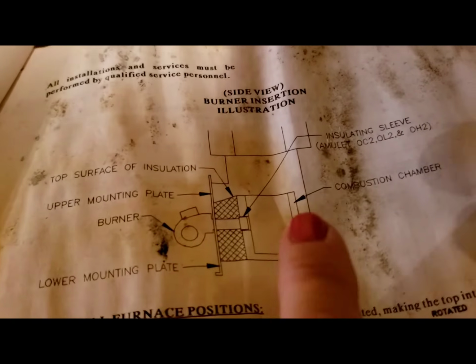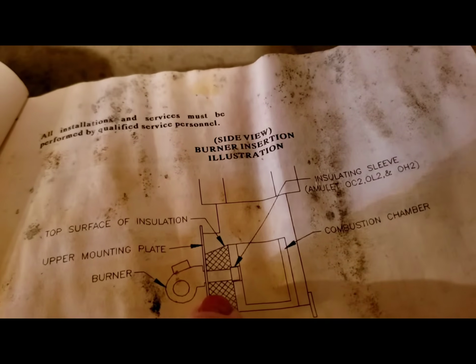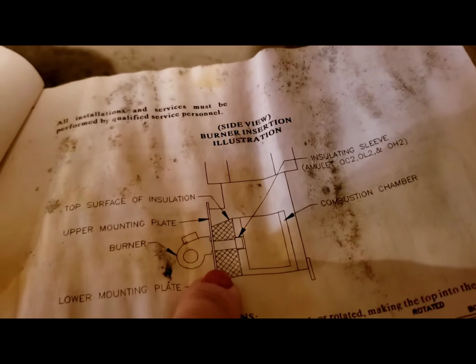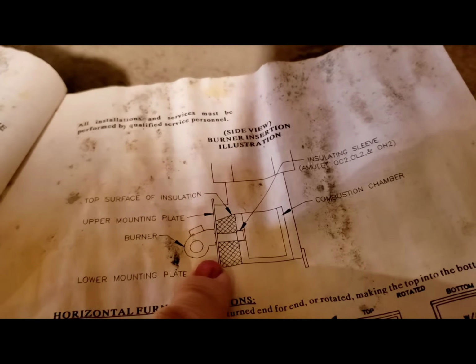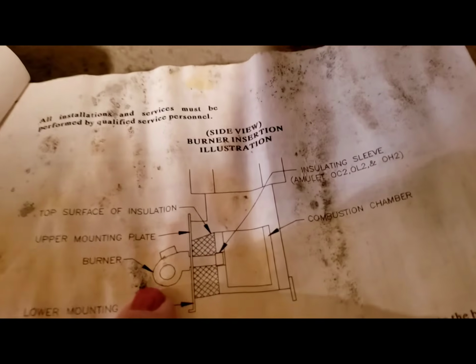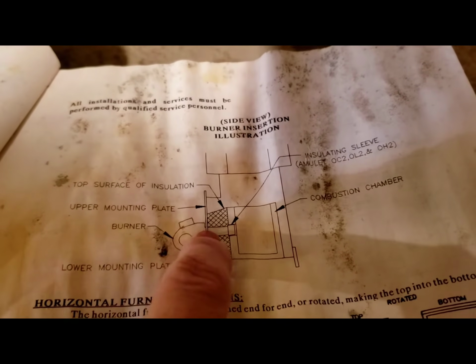What he found in doing this is this cross-stitched stuff is insulation, a special ceramic insulation that's basically fire resistant or fireproof. It's supposed to go above and below this burner outlet, and it protects your burner from overheating.